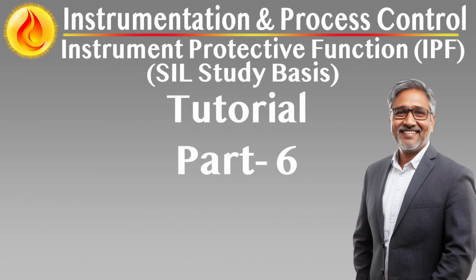Approved protocols and network considerations. Safety-certified protocols for critical links. When communication is part of the IPF logic, e.g., distributed logic solvers, only safety-rated protocols, such as ProfiSafe, SafetyNet, or SIL-rated Modbus variants, may be used.